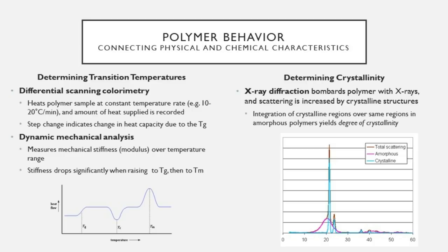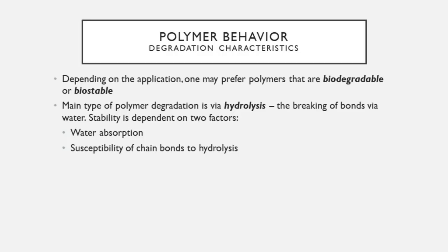The physical properties of a polymer may change over time, especially in the body, depending on whether it's biodegradable or biostable. Which one we want depends on the application. A load-bearing implant meant to last decades requires a biostable polymer. However, a tissue scaffold meant to be replaced by the body's healthy cells during wound repair should be biodegradable — preferably on the same timescale as the wound healing process.